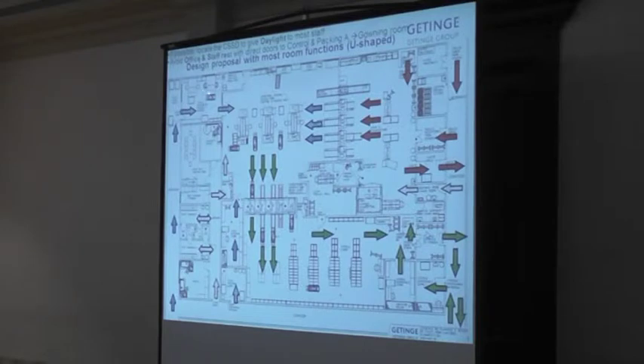Sometimes I see plans to have linen inspection in the packing area. That is completely forbidden. Here is ISO class 8, a very clean area. So we shall keep it that way and separate with a door here. And here we wrap the items and put them in a basket. And then we sterilize the items. So that should really be its own area. This is something we need to think about as well. It's not uncommon to see that the clean materials are forgotten completely.